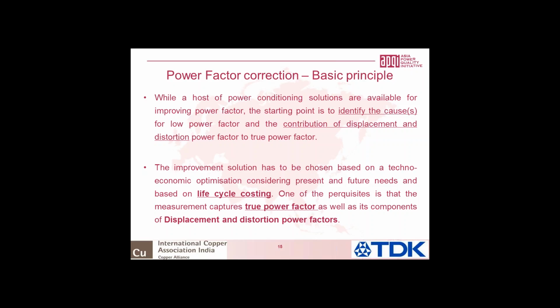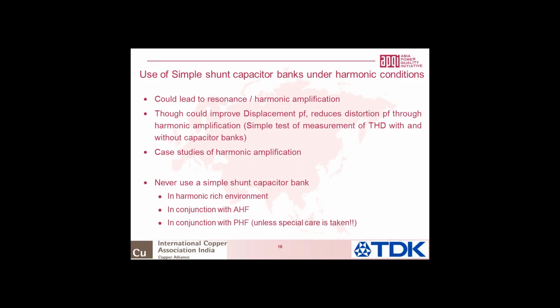And this is based on life cycle costing. Any equipment we buy will have various cost elements like the capital cost, the running cost, the installation cost, the maintenance cost, spare cost, and cost of disposal. And in my opinion, every decision, not just an energy efficient motor, not just a two-wheeler with a higher mileage, even for power conditioning devices, the choice should be based on life cycle cost and not on capital cost. So one of the prerequisites is that we not only compensate for displacement power factor, we compensate the true power factor, and the choice of the solution from the list we just saw is based on life cycle costing.